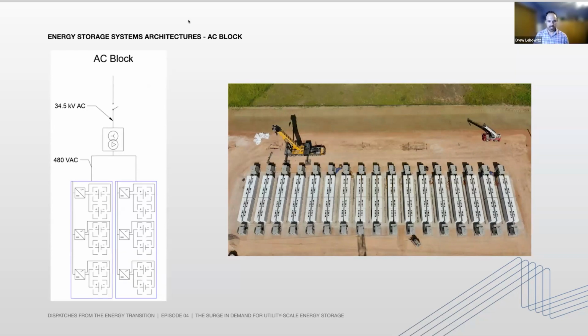And the difference is this: if we look at those blue boxes on the bottom of the single line, those represent the enclosure. Inside the enclosure, you have many small inverters or PCSs, coupled with sometimes a few racks or sometimes a few modules. It just depends, but you'll have some amount of DC energy in a battery coupled with an inverter, and that is repeated several times in each enclosure.